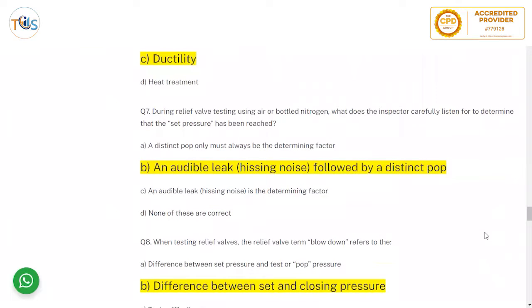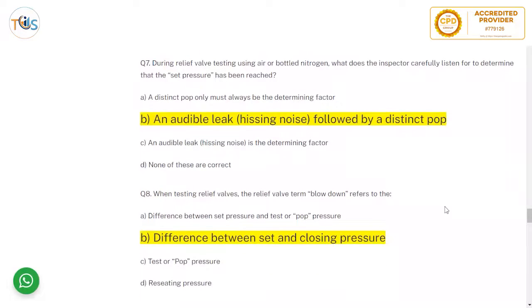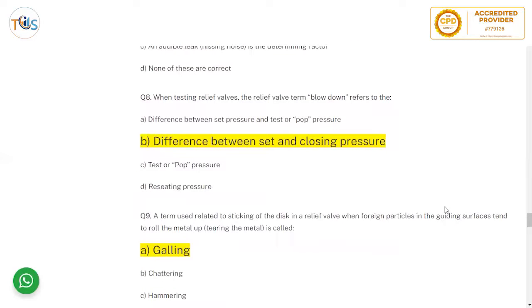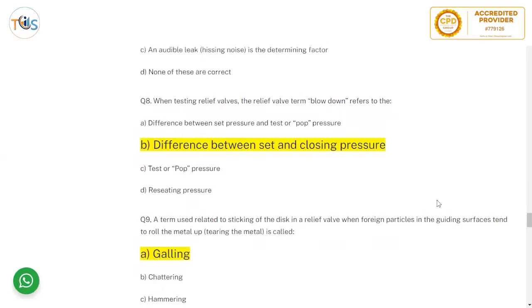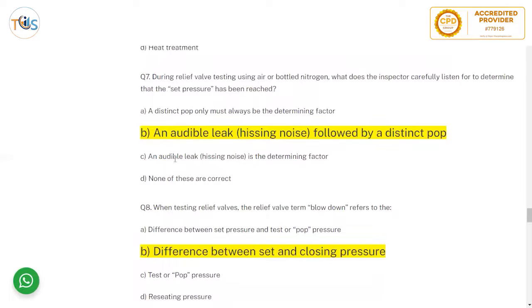Sample question: During relief valve testing using air or bottled nitrogen, what does the inspector carefully listen for to determine that the set pressure has been reached? The answer is an audible hissing or leak sound, followed by a sudden pop — similar to a pressure cooker. This is the most appropriate and complete answer, as eventually the hissing leads to the valve suddenly popping open.